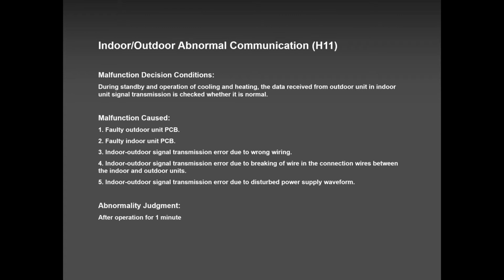Okay, let's start with H11. So H11, if there was no pandemic and we were allowed to go into a training session and all that, I would give you guys to do it hands-on. I would give you to create H11 and fix it. And how would I do that? H11, basically, it's a communication error. The indoor and outdoor are not talking to each other anymore. So now the indoor unit is displaying this error code H11. It is displaying after you retrieve it.